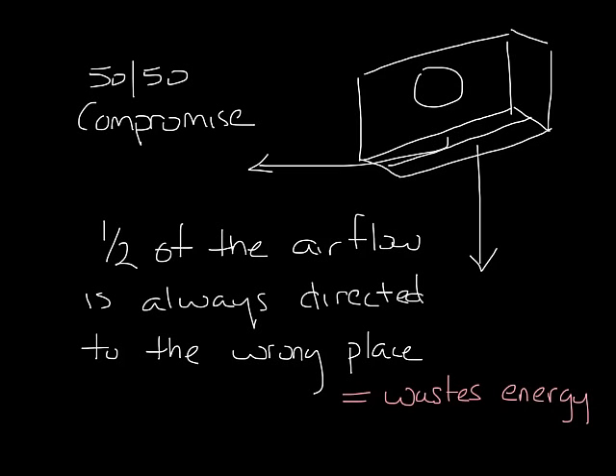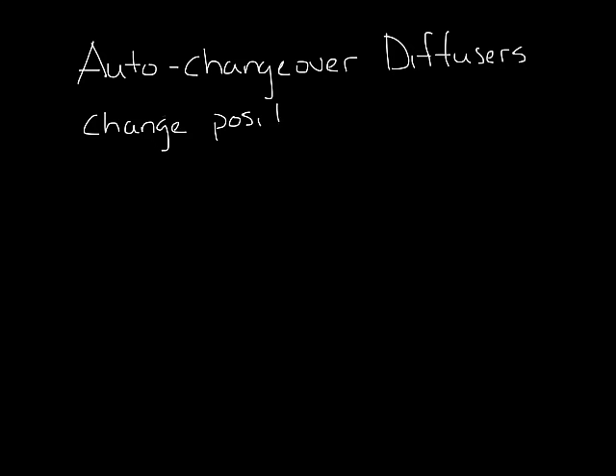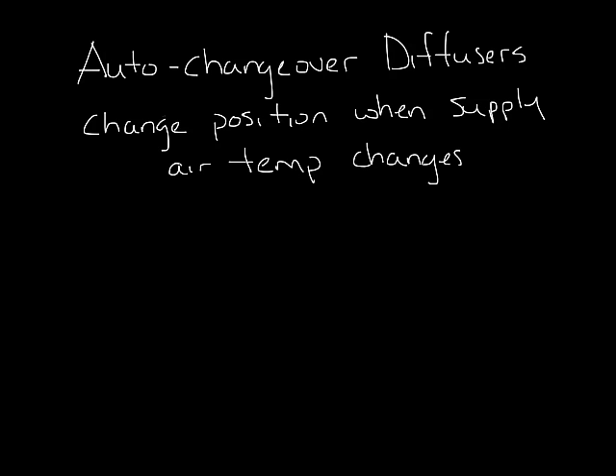So wouldn't it be great to have a slot diffuser change positions by itself? Well that's exactly what auto changeover diffusers do. They change the position when the supply air changes temperature. Titus makes a couple auto changeover diffusers. They all do basically the same thing which is switch the airflow pattern from cooling position to heating position when they sense a change in the supply air temperature.